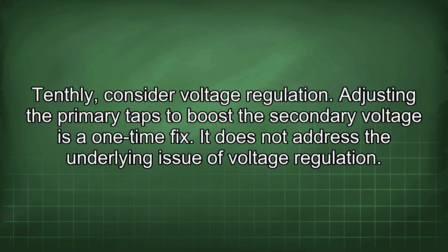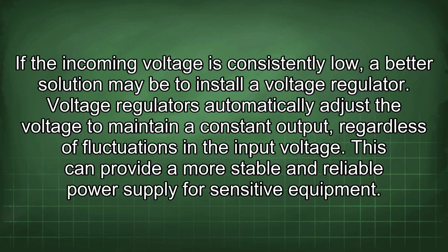Tenthly, consider voltage regulation. Adjusting the primary taps to boost the secondary voltage is a one-time fix. It does not address the underlying issue of voltage regulation. If the incoming voltage is consistently low, a better solution may be to install a voltage regulator. Voltage regulators automatically adjust the voltage to maintain a constant output, regardless of fluctuations in the input voltage. This can provide a more stable and reliable power supply for sensitive equipment.